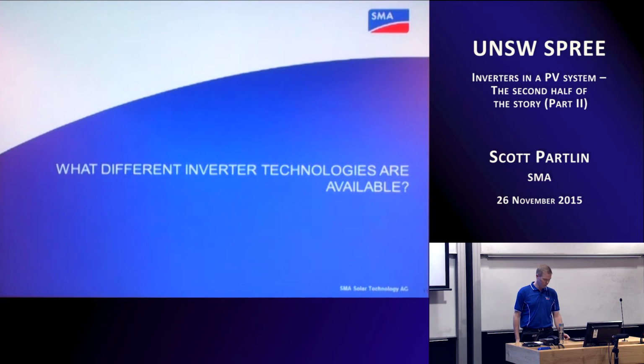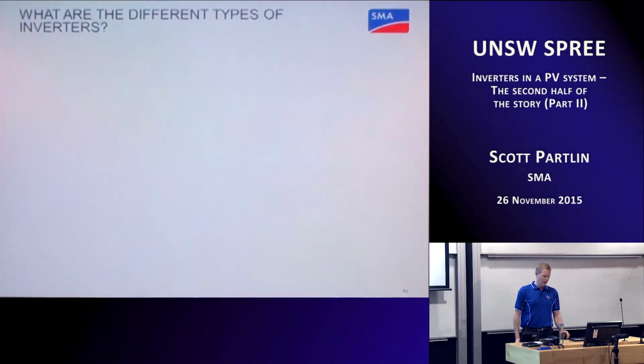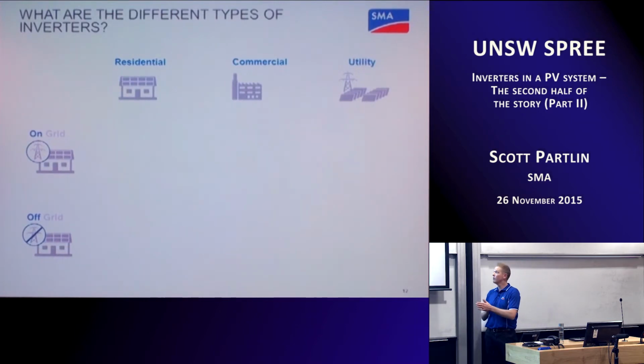So what different inverter technologies are available? When you look at inverters and what's out there, before you look at the different actual technologies, you need to look at where they're used. And in terms of where they're used, that's pretty much it. You've either got on-grid situations where the inverter is connected to a distribution network or a large grid or even a microgrid, or you've got off-grid installations. For each of those, they can be at any scale: residential, commercial, and utility scale. But the technology for each of those applications changes. There are obviously different requirements at each of those market segments and applications, and accordingly the technology has to change to meet those.